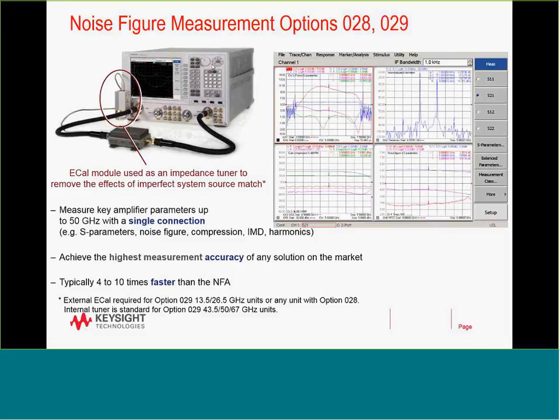The technique is usually up to 2 times faster than the noise figure analyzer technique in many cases. However, because of the PNA and network analyzer capability of making many measurements in a very small span of time, customers are seeing a lot more details because we can actually do some very narrow frequency spacing in the sweeps.